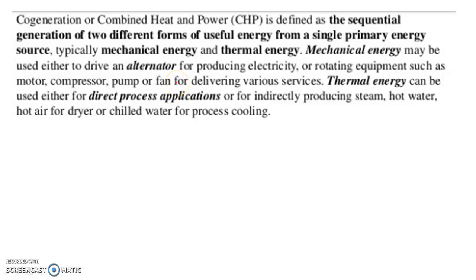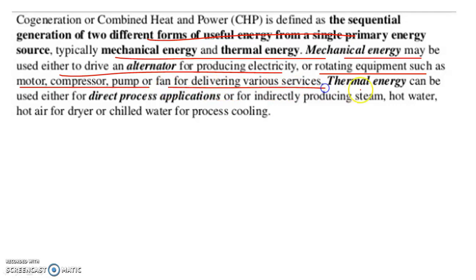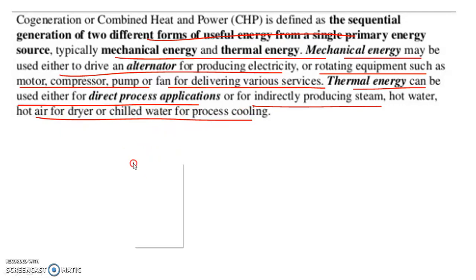Another one that we have seen in power plants, cogeneration or combined heat and power, is defined as the sequential generation of two different forms of useful energy from a single primary source, typically mechanical energy and thermal energy. Mechanical energy may be used either to drive an alternator for producing electricity or rotating equipment such as a motor, compressor, pump or fan for delivering various services. Thermal energy can be used either for direct process applications or for indirectly producing steam, hot water, hot air for dryers, or chilled water for process cooling.